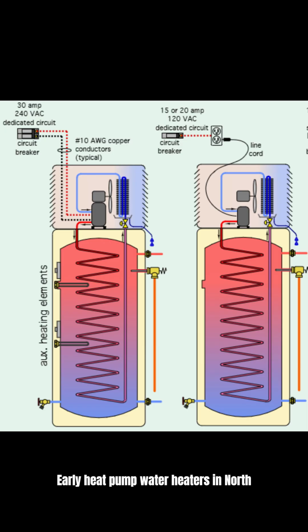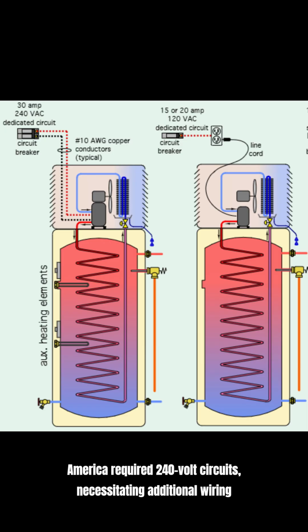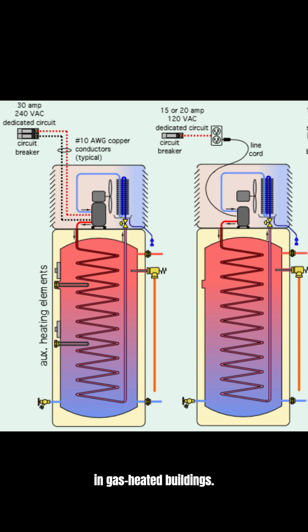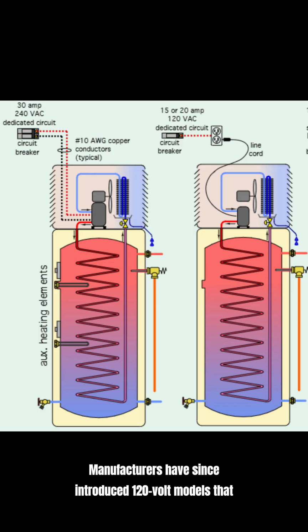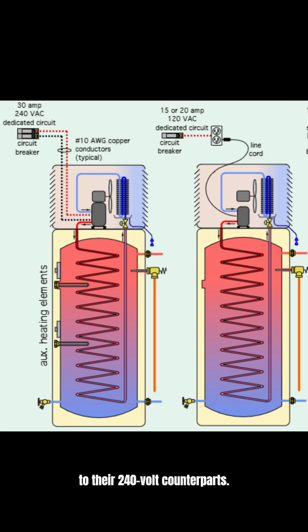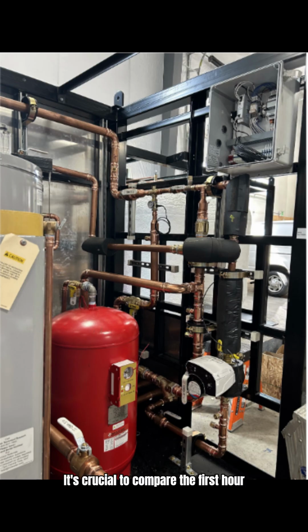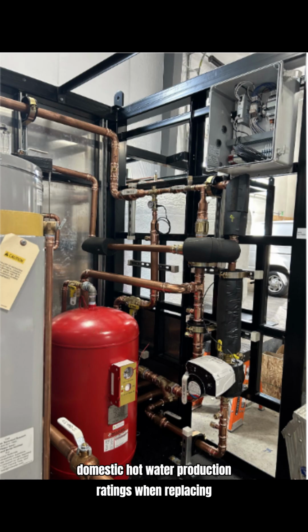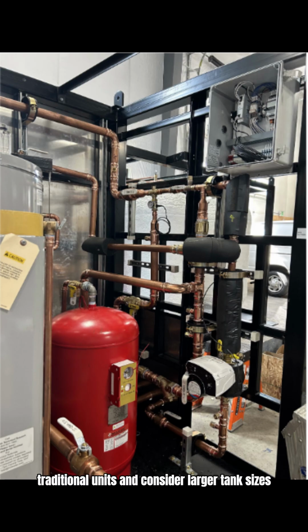Early heat pump water heaters in North America required 240-volt circuits, necessitating additional wiring in gas-heated buildings. Manufacturers have since introduced 120-volt models that utilize existing circuits, reducing installation costs, although these models have lower recovery rates compared to their 240-volt counterparts. It's crucial to compare the first-hour domestic hot water production ratings when replacing traditional units and consider larger tank sizes or higher storage temperatures to meet demand.